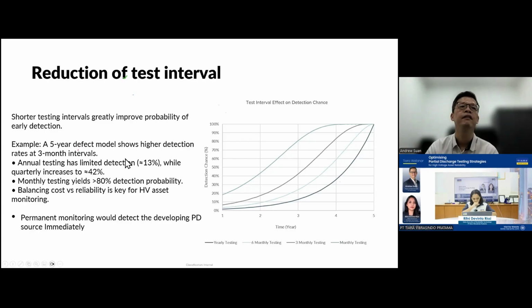For example, a 5-year defect model shows higher detection rates at 3-month intervals. If you do annual testing, you'll most likely detect the problem at only 13% by the third year. If you do monthly testing, there's an 80% chance you'll detect it by the third year. So with yearly testing, the chance of discovering the PD early is only 30%, very low. But if you go monthly, you'll capture 80% of PD activity. Then somebody may ask, how about if I want 100%?